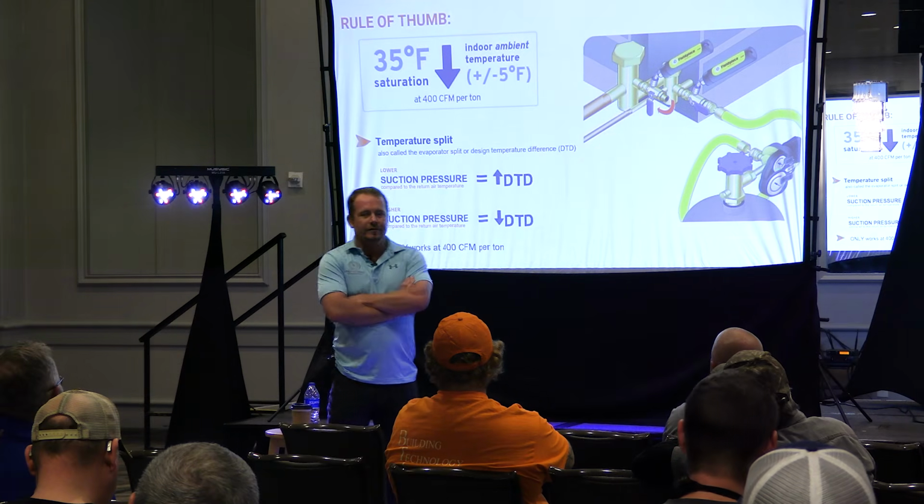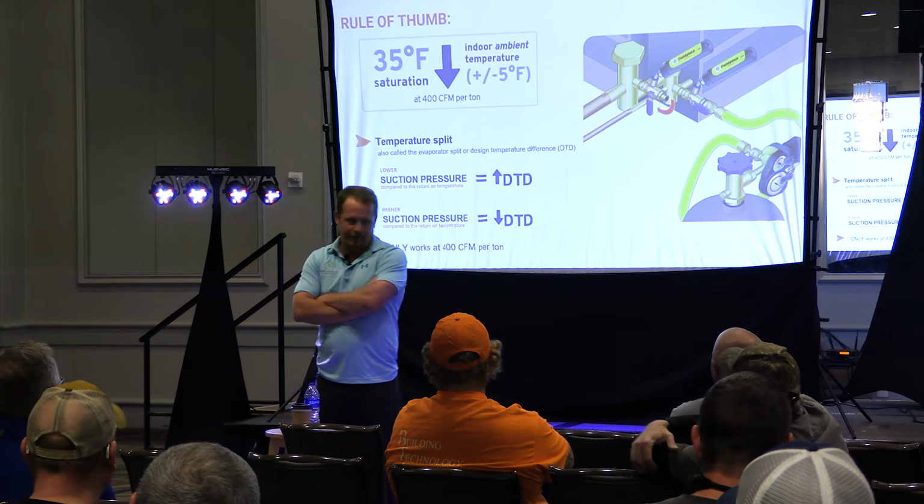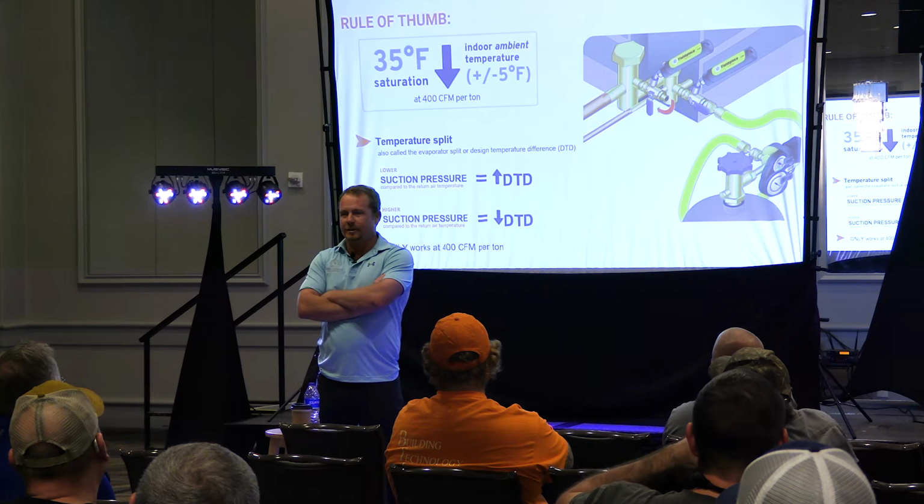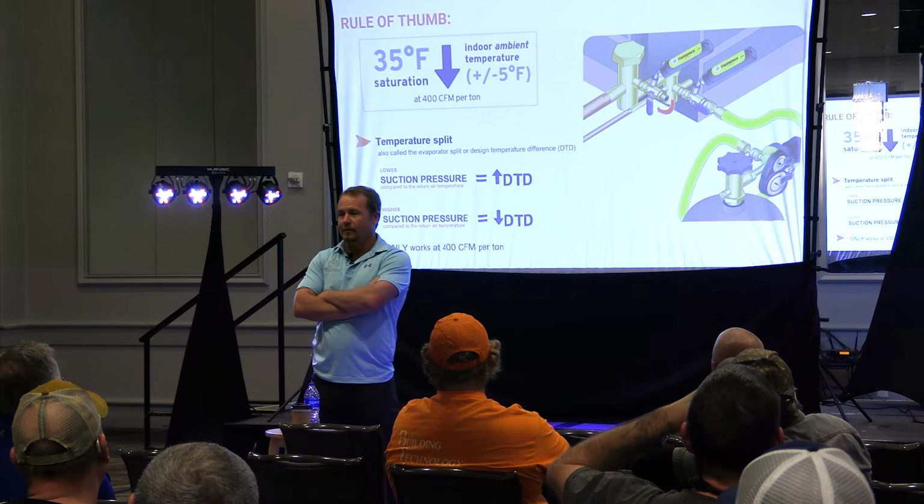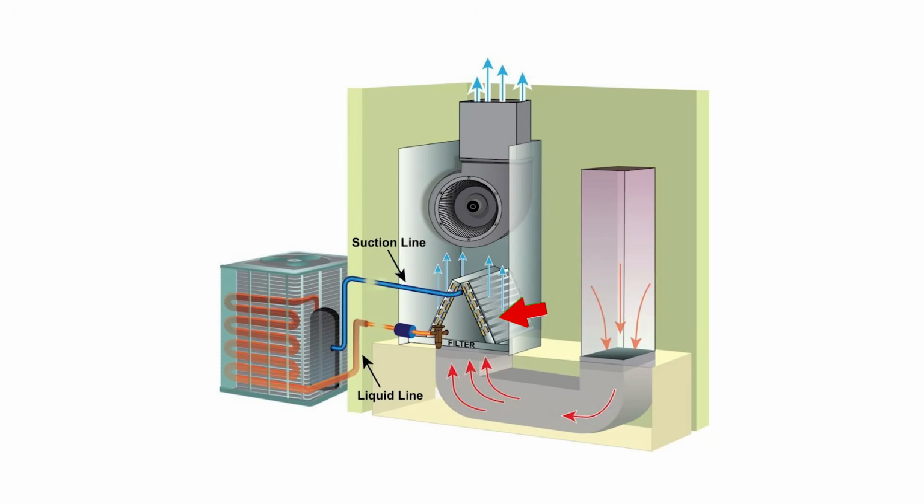But once you recognize that the pressure number means nothing, it's the saturation temperature, the boiling or condensing temperature that it represents, that matters. On the suction side, it's the boiling temperature, the evaporator temperature. On the high side, on the liquid line specifically, it's the condensing temperature.